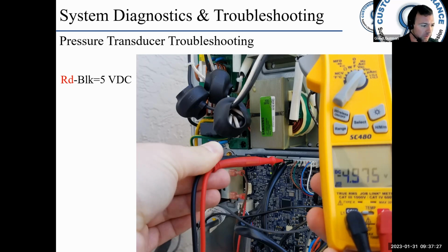So let's see. The expansion codes 01 and 41 explain the type of issue. In that case, it was an open, meaning the signal wire is returning more than 4.5 volts DC. Most likely the cause is the sensor wire being disconnected and the PCM board is pulling up the voltage signal to supply 5 volts. Expansion codes 02 and 42 indicate that it's a shorted, meaning that the signal wire is returning less than 0.5 volts DC. When a DC value of 4.8 to 4.9 is returned to the PCM, it will trigger the 5743 and 5843 faults.